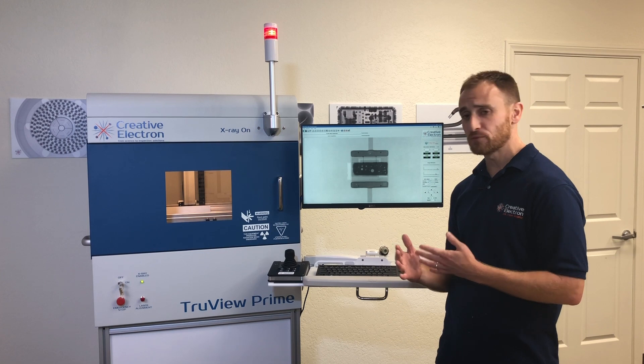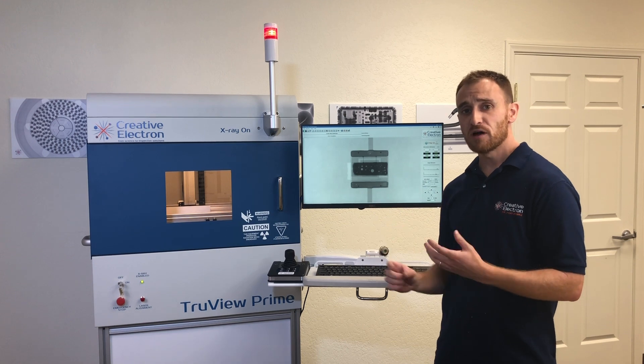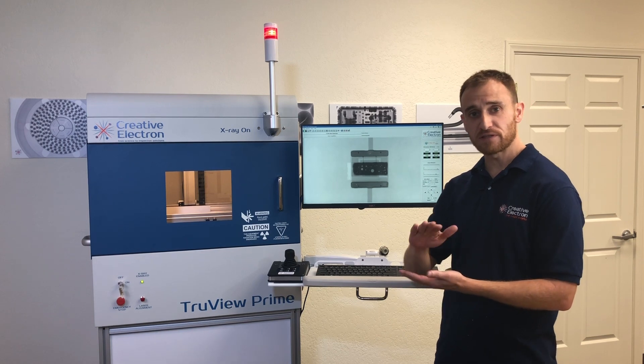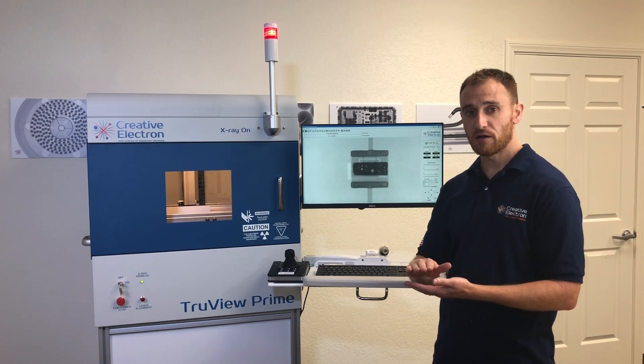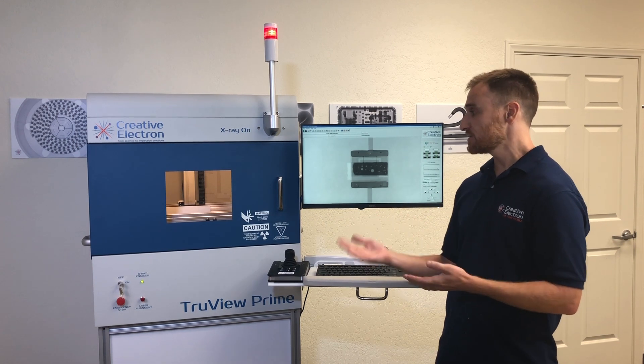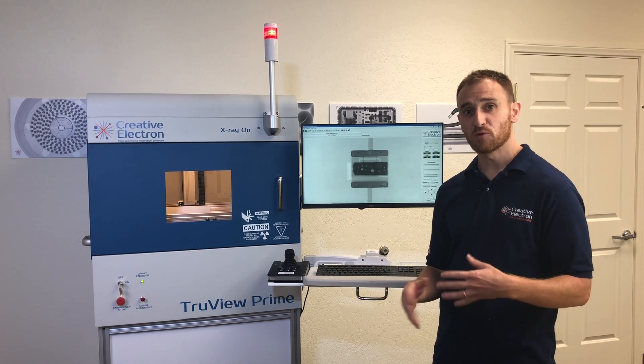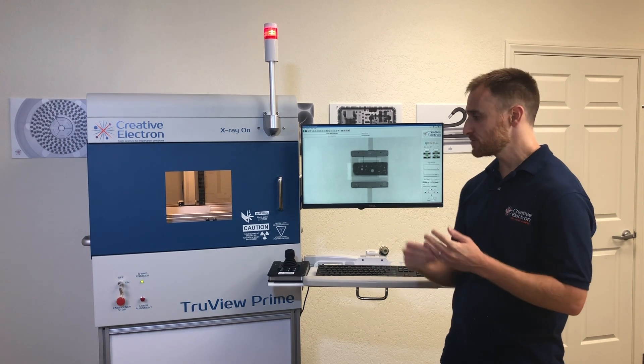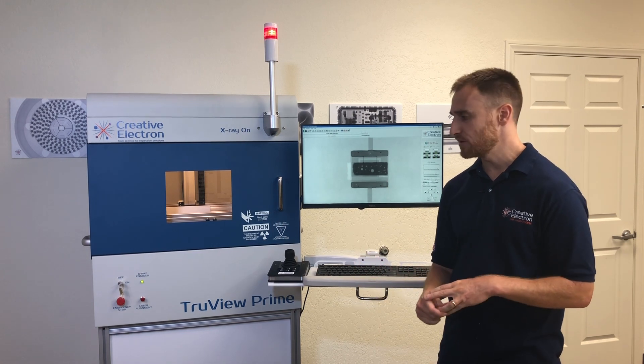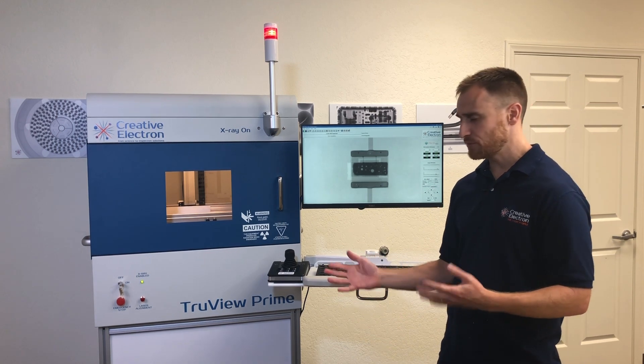Different options that the TruView Prime can be equipped with include a reel-to-reel automatic acquisition setup where we can acquire images of every single part on your reel. We can also put a sample rotation stage in there where we rotate your sample and automatically acquire images every degree or partial degree. We can also put a stage tilt in there to get nice oblique views, representing more of a 2.5D x-ray application. As you can see, the TruView Prime is sitting on top of a cart, which is another option we offer to customers to improve mobility around your shop or lab.